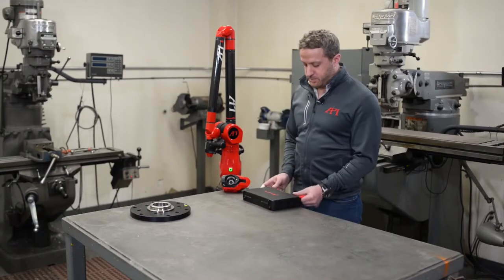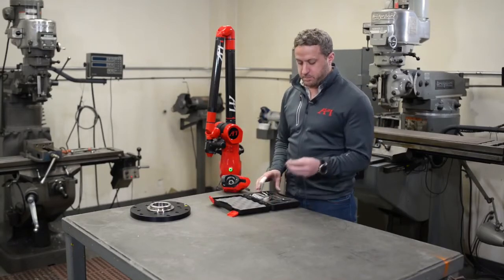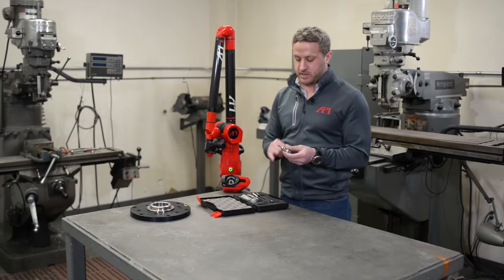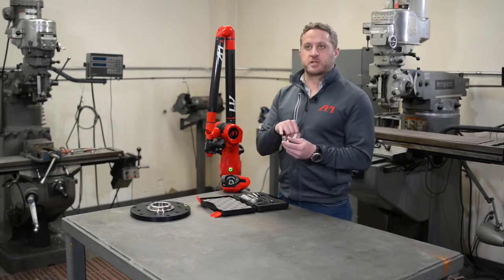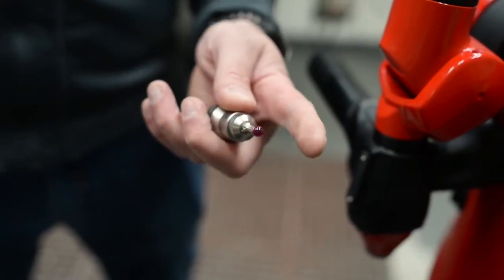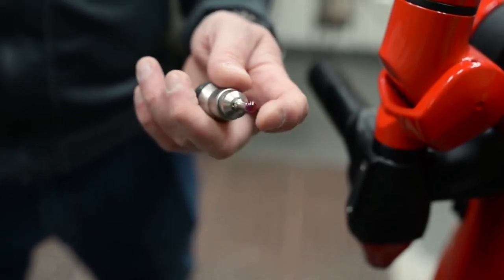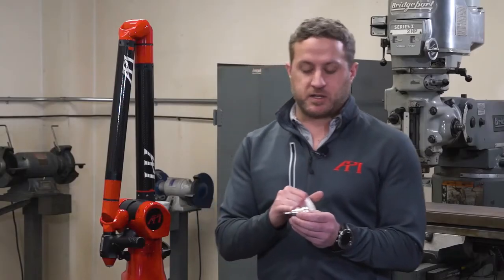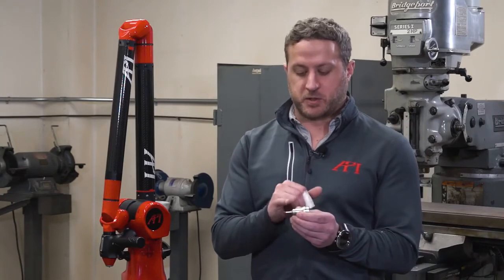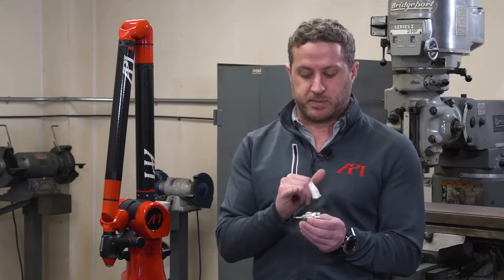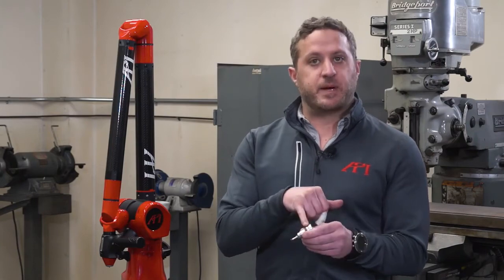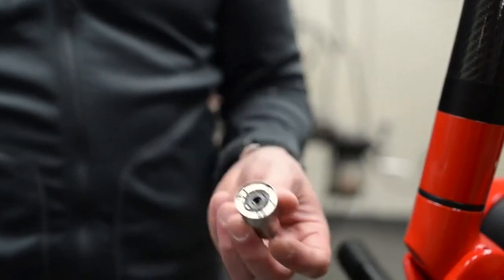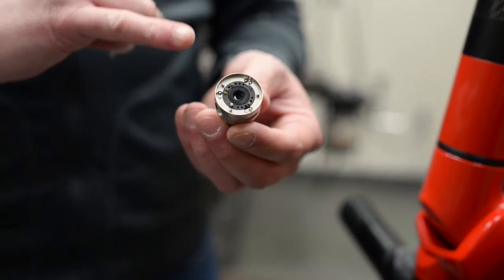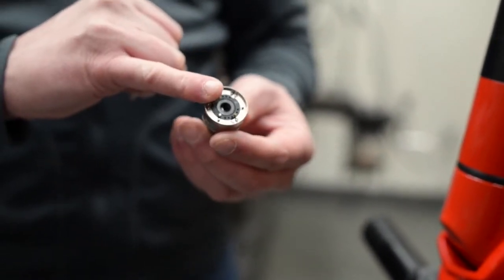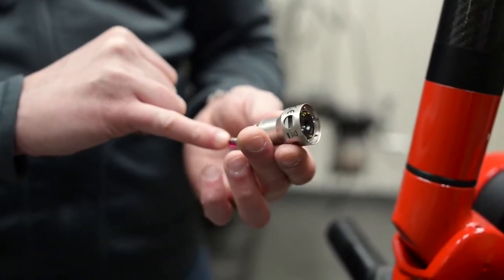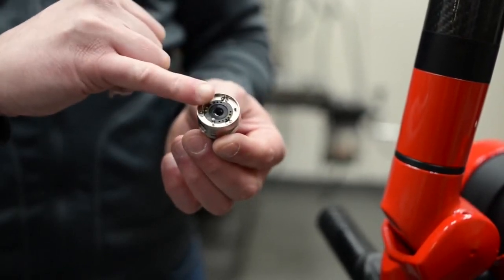Inside the kit, I am going to pull out the probe that comes with it. This is a standard kit where it includes a 6mm ruby tip. The nice part about these ruby tips is that it's modular for the whole base attachment. There's 3 components to it: the actual tip, a spacer, and the base. This base has data information inside of it that will carry your calibration of that probe no matter what computer you go to. It's all stored in the probe.